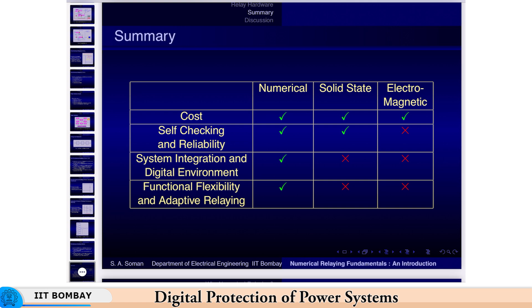Okay, and finally some thoughts that I will leave you with, so that you can think of answers for this yourself. Can relaying hardware or protection hardware be used for measurement purpose? Either way. Remember that in relaying the currents can be very high, while in measurements you need to accurately measure even the smallest of currents. So for example, if we talked of a 12-bit ADC, the resolution at the bottom of the scale could be poor. In which case you may not be able to measure a current as low as 1 ampere when you have to measure currents as high as say 10,000 amperes.